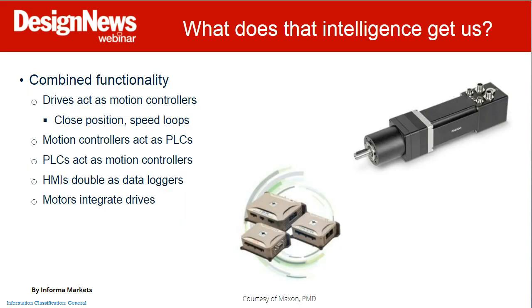So the intelligence has enabled components to do a whole lot more. The classic model is your PLC runs your machine logic, the motion controller does your motion control, it tells the drives how to commutate the motors, your feedback devices tell you how well you're doing to help close the loops. Well, these days you've got drives that have motion control capabilities, motion controllers that can do machine logic, PLCs that can do a few axes of motion control, HMIs that can be data historians, and integrated motor drives that can do it all. So these functionalities can really start solving a lot of problems for us.